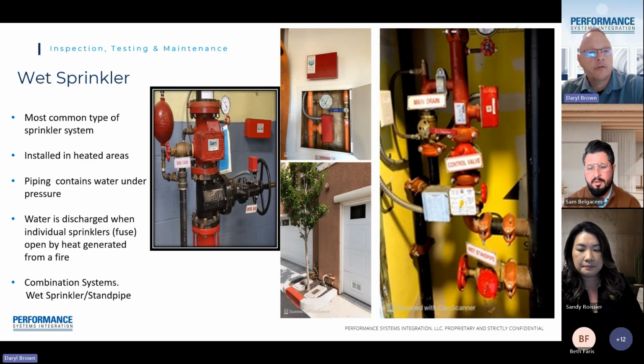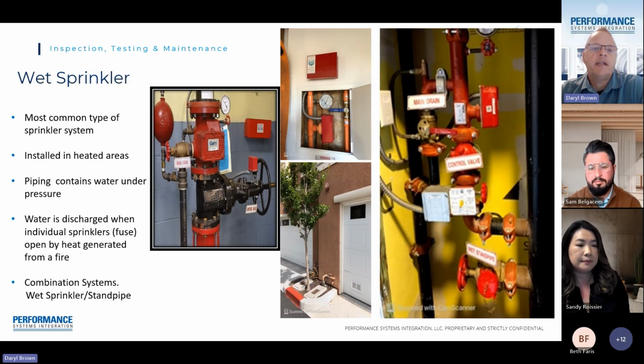So, fire sprinkler riser systems. These are basically piping components that are feeding fire sprinkler heads. So this is a water distribution center. As you see there on the left-hand side is a basic riser. When you hear that terminology riser, basically it's the pipe coming in and feeding out to fire sprinkler heads. There in the middle is a different style. It's more of a residential style. Same basic components, just in a wall hatch. On the right-hand side, if you walk into most multi-story commercial buildings, this is probably what you'll see in the stairwell. This is the basic riser setup for a fire sprinkler system in a commercial building.